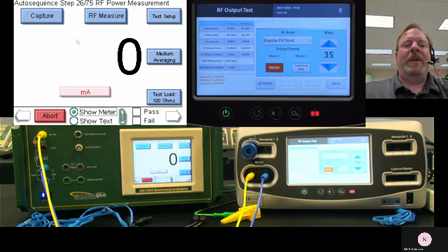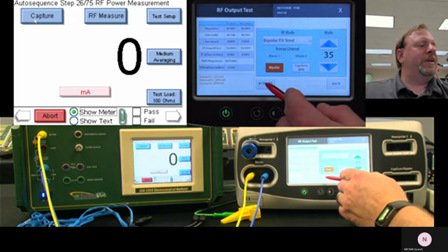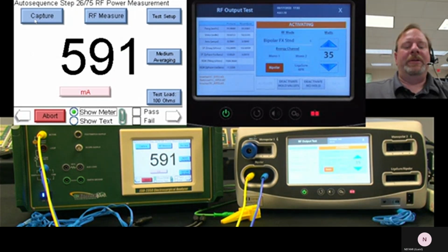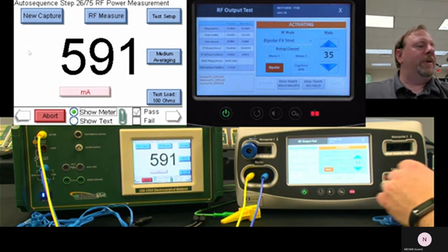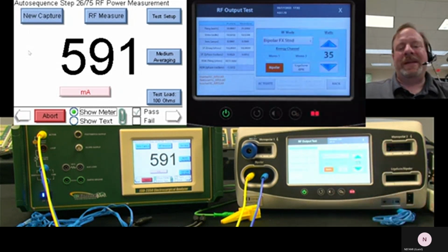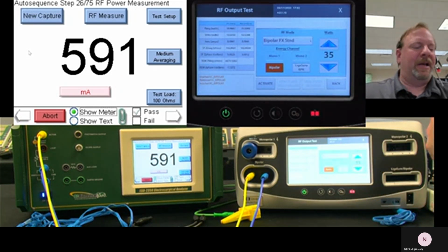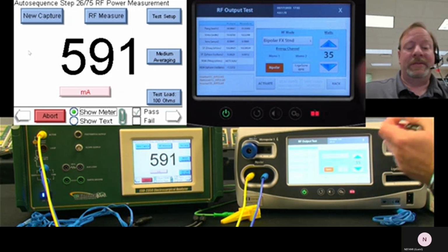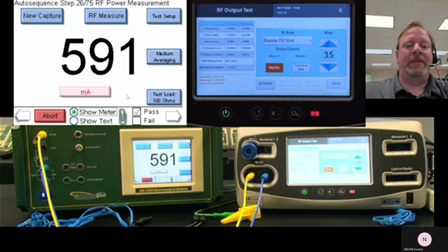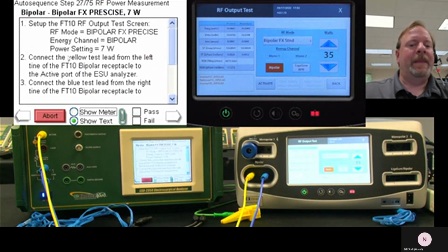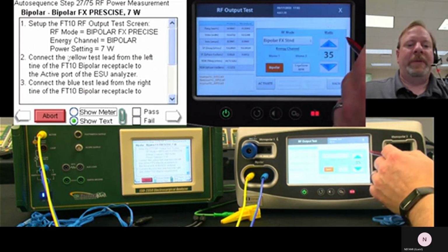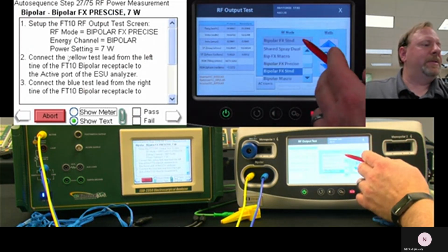I wanted to show you the medium averaging. So I'm going to activate the generator, and there's our reading. That's medium averaging. It's really not moving around very much. It's a nice, good, stable reading, so we can capture that. And that's why I say you can use medium or fast. Fast pretty much works with everything on this particular analog circuit that is in the 2350. So FX precise.